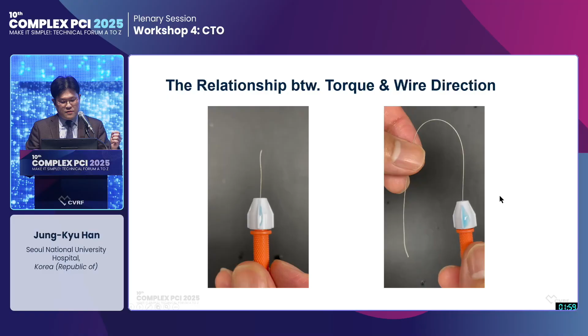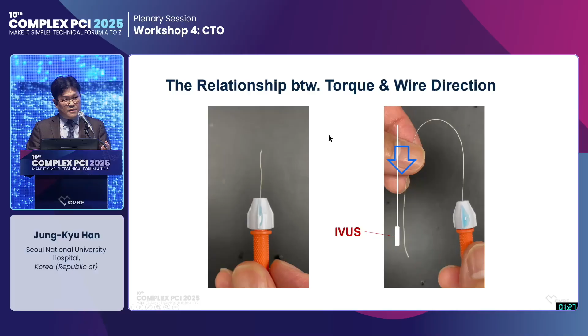But you don't need to worry about that because the IVUS catheter is always located nearby the wire tip. And the projection is from proximal, looking at the distal. So when you make a clockwise torque on your hand, you will see a clockwise rotation on the IVUS. And when you make a counterclockwise torque, the wire always moves counterclockwise. So the direction of the torque is always the same as the direction of the wire tip on the IVUS. So it's very easy now. The concept itself is easy.